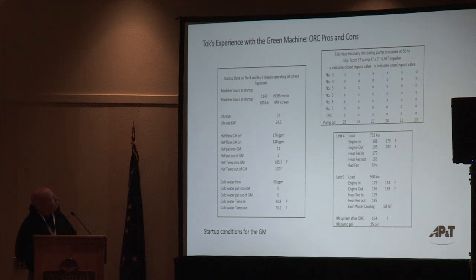This matrix up here is the status of the valves in the heat recovery system. As I discussed, we put isolation valves on all the different exchangers so that we could bypass them and avoid the heat losses that might occur by running the heat recovery fluid through those exchangers. This is the two units. This was when this startup occurred. We were running unit 4 and number 9, and this was the conditions of 4 and 9 at that time.